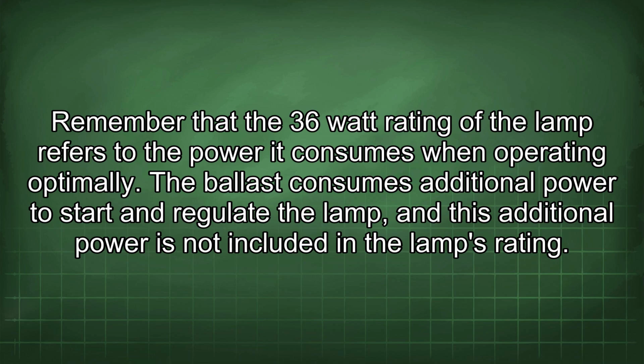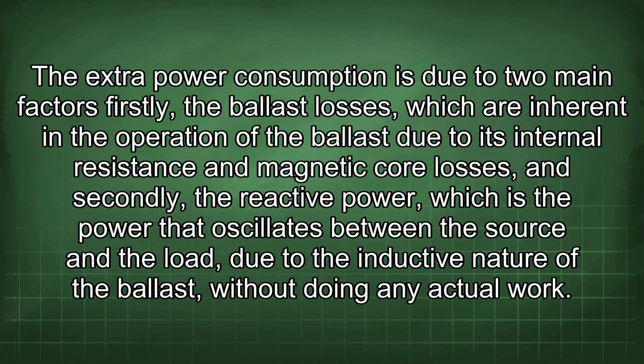The ballast consumes additional power to start and regulate the lamp, and this additional power is not included in the lamp's rating. The extra power consumption is due to two main factors. Firstly, the ballast losses, which are inherent in the operation of the ballast due to its internal resistance and magnetic core losses, and secondly, the reactive power, which is the power that oscillates between the source and the load due to the inductive nature of the ballast, without doing any actual work.